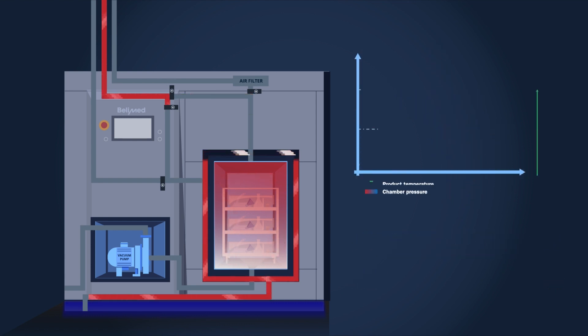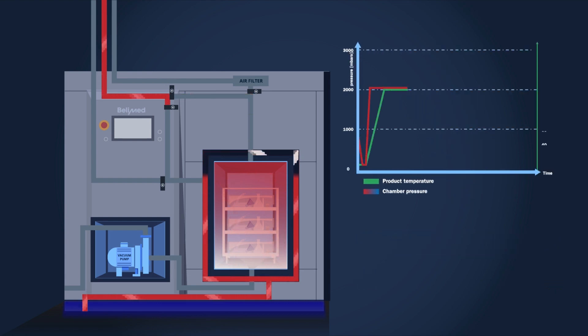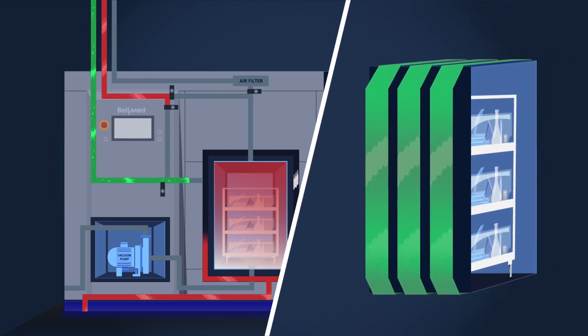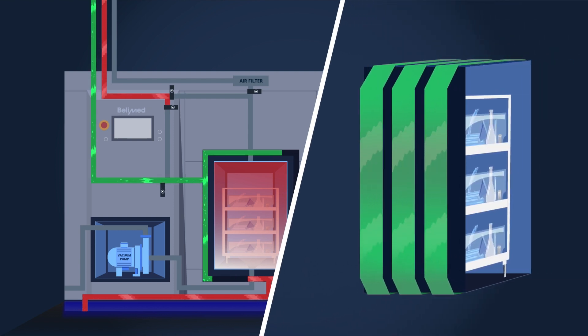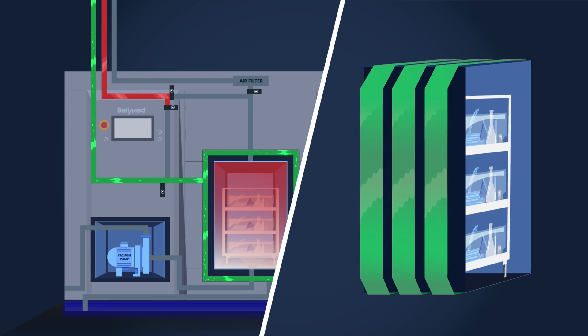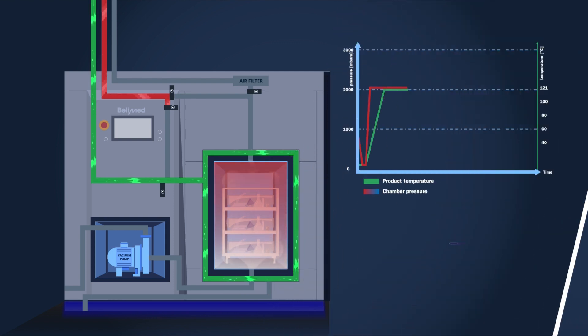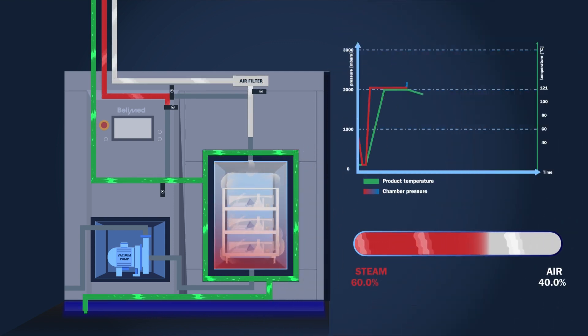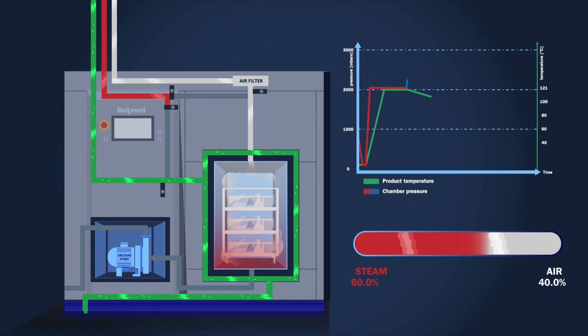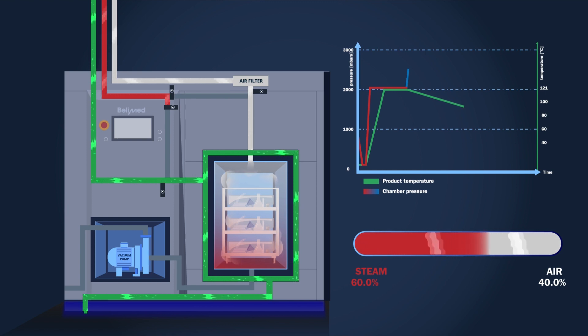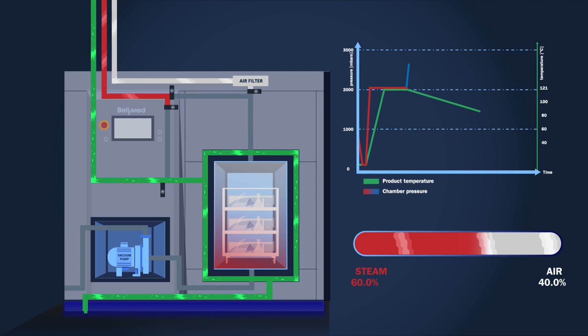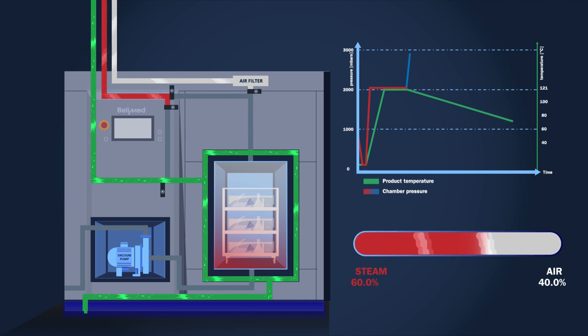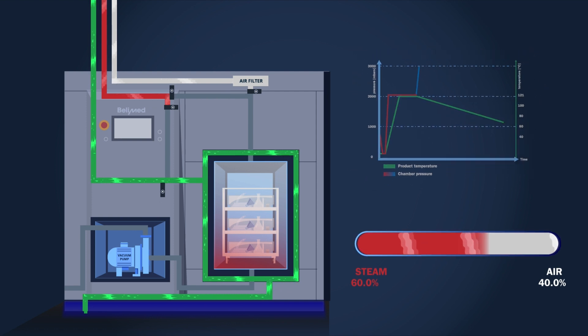After the sterilization phase, it is time to cool the sterilized goods. To cool the sterilizer and the products, the channels outside the chamber are flushed with cooling water. Additionally, pressurized air is added inside to increase the pressure to avoid liquids boiling and evaporating. The cooled chamber walls cool the steam air mixture inside the chamber, so the chamber and products cool down.